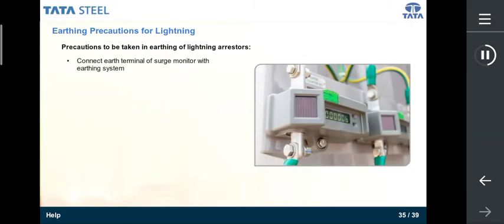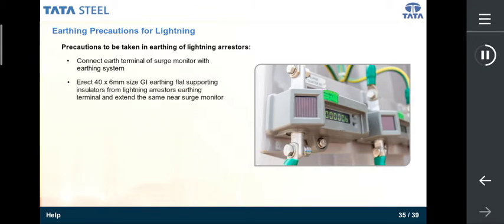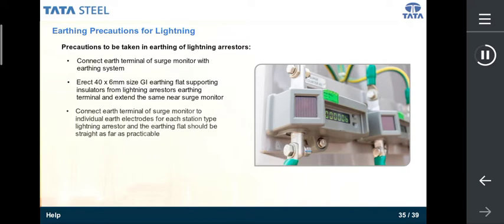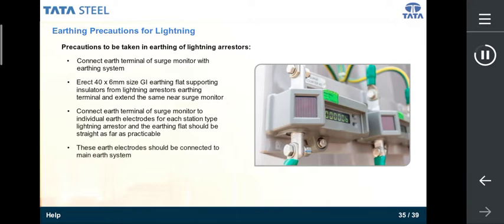Connect the earth terminal of the surge monitor with the earthing system. Erect 40 by 6 mm size GI earthing flat supporting insulators from the lightning arresters' earthing terminal and extend the same near the surge monitor. Connect the earth terminal of the surge monitor to individual earth electrodes for each station type lightning arrestor, and the earthing flat should be straight as far as practicable. These earth electrodes should be connected to the main earth system. Ground connection of the surge monitor shall be made firmly before connecting the same near the surge monitor.